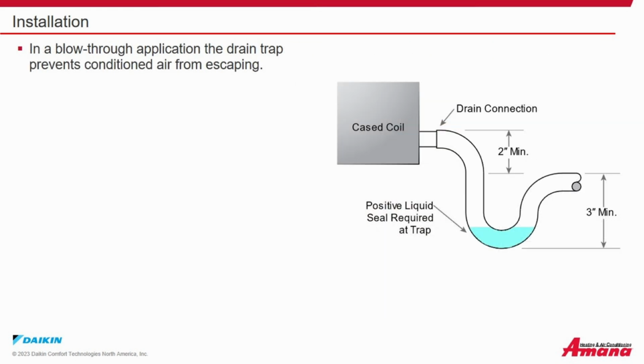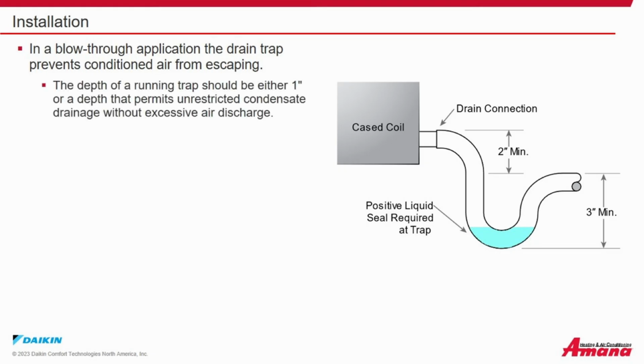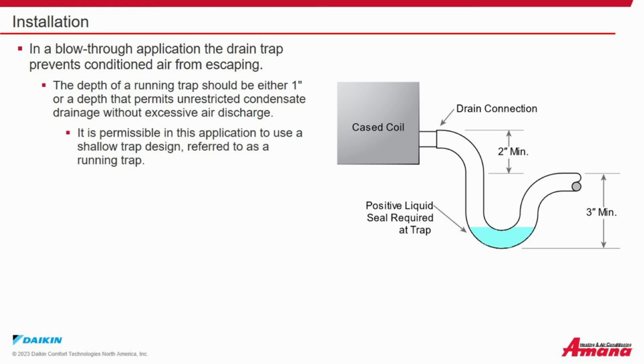In a blow-through application, meaning the coil is mounted on the discharge side of the air handler or furnace, the drain trap prevents conditioned air from escaping. The depth of a running trap should be either 1 inch or a depth that permits unrestricted condensate drainage without excessive air discharge.